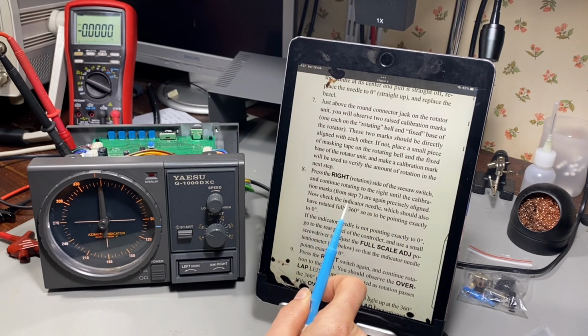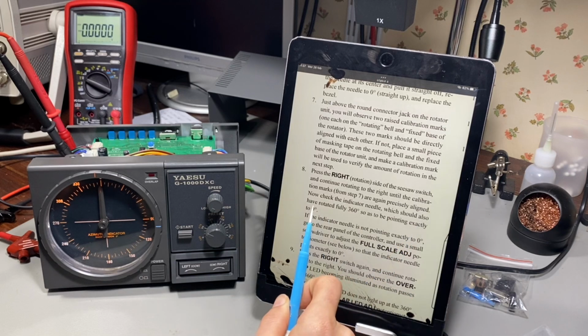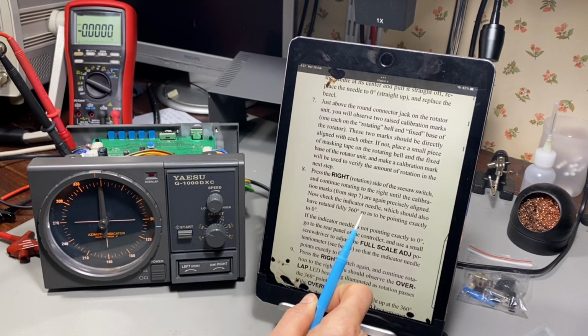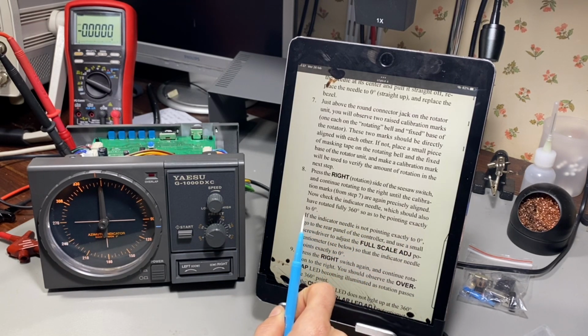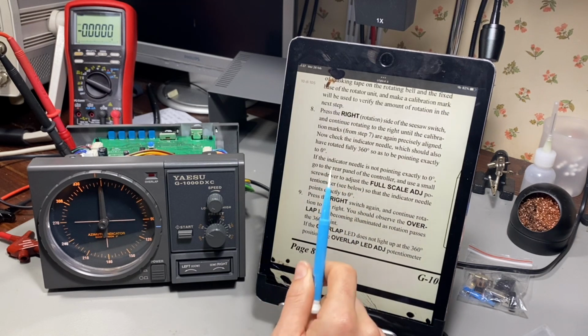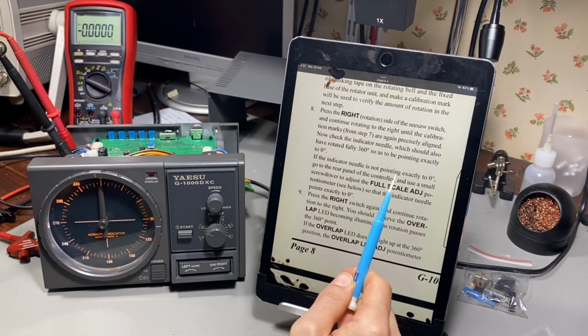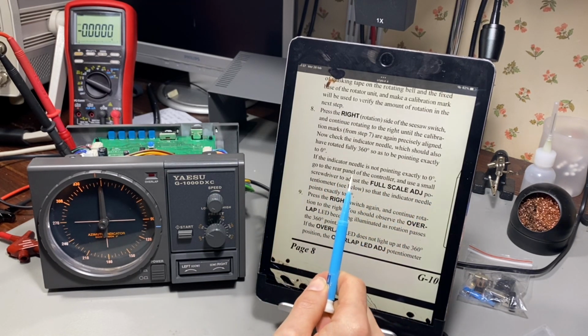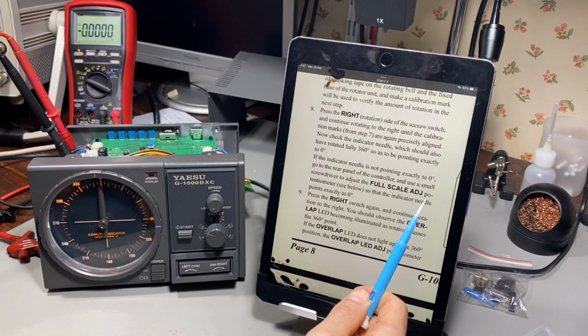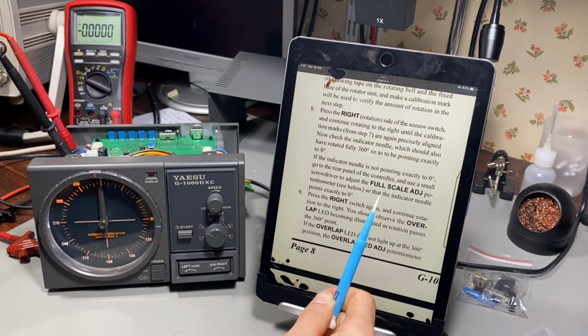Now check the indicator needle, which should have rotated fully 360 degrees so as to point exactly to 0. If it's not pointing exactly to 0, go to the rear panel of the controller and use a small screwdriver to adjust the full scale adjust potentiometer so the needle points exactly at 0. That will be the next step.